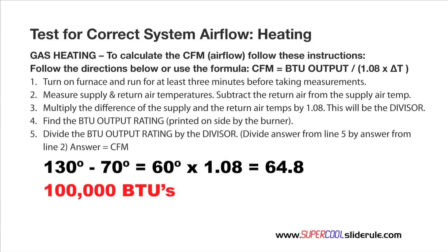We are going to divide that by our divisor, which we just calculated earlier, which was 64.8. Do the math on this, we come up with 1,543. Plain and simple, that is our CFM through this furnace.